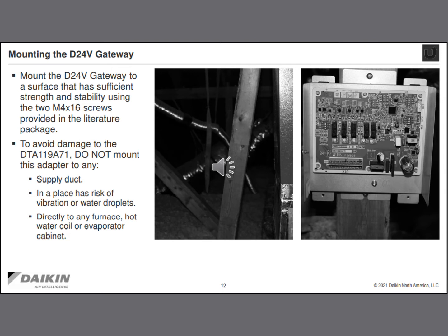It can be mounted to a return air duct, or it could be mounted to a structural framing member or wall near the HVAC equipment. Now, I know there's many applications out there where we don't have this nice flat surface that we can attach an adapter to right next to the equipment, so sometimes we have to mount it where we can mount it. Just make sure it's mounted in a place that you're not going to face condensation, extreme temperatures, or vibration. If we can avoid those three, we'll be in good shape.